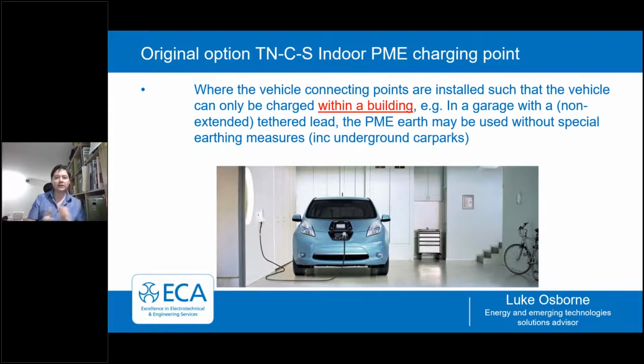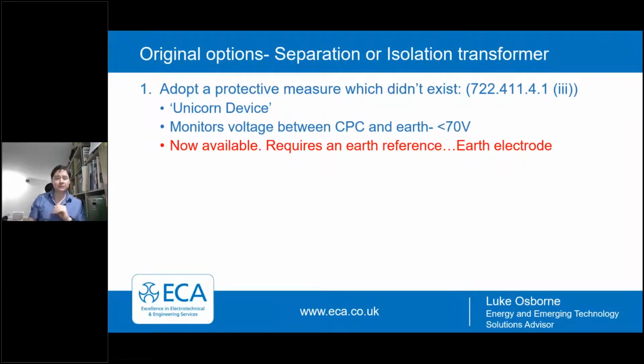Okay, so I've said when it's a TNCS, there needs to be special considerations. If the charge point is going to be installed within a building, perhaps an internal garage or an underground car park, then PME can be used without special earthing measures, so long as the charge cables don't extend out beyond the realms of the premises to outside, so outside a garage, etc. So that is an acceptable time to use PME. But in the other instances, the original options from 722 do still apply.